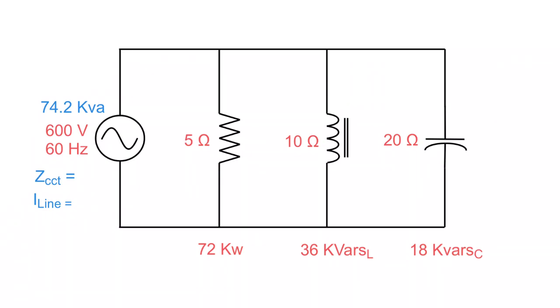So now we've got this 74.2 kVA. We've got 600 volts here. The first thing we're going to do is try to work out what our current is. We've got a source voltage of 600 volts. We've got your kilovolt amps over here, your apparent power. So I'm going to take 74,200, divide that by 600, because it's power divided by voltage gives me current. In this case, that works out to be 124 amps.